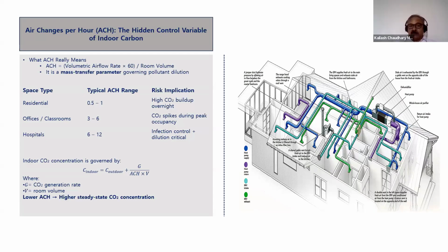In a steady state model, indoor CO2 concentration is inversely proportional to the ventilation rate. In an ideal steady state condition, if we treat a room as a well-mixed control volume, the steady state concentration is always equal to the generation rate divided by the ventilation rate and the volume. If you reduce ventilation, the CO2 will increase. If you increase ventilation, CO2 will fall. This principle underpins the global ventilation standard, which is there as of now.